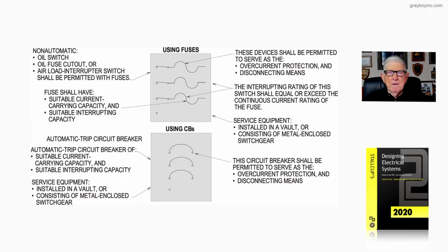voltage equipment, we refer to Article 311. If we're picking up the ampacity of conductors based upon conductors in conduit and free air or in the ground, or cables in the same manner in some cases, then we also go to Article 311. But when we select components and equipment like switchgear, switchboard, panel boards, and the overcurrent protection means that we select, 490.21 and 490.22 is used also. You know, we have a window, that kind of thing.